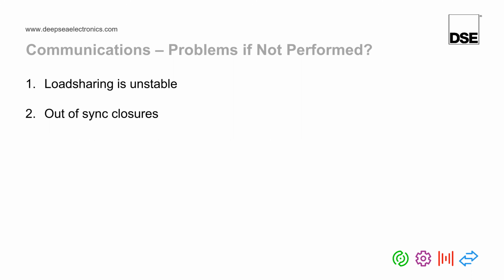Just looking at one of the questions that's just come in, it says, what happens if the MSC link fails? For example, the wire is cut. Well, if you only use one MSC link, and I'll come back to what I mean by that in a second, then the modules will no longer communicate. And as you can see here, you potentially may have out-of-sync closures, or no load sharing will work whatsoever. You could end up having reverse power trips, loss of excitation trips, lots of problems.